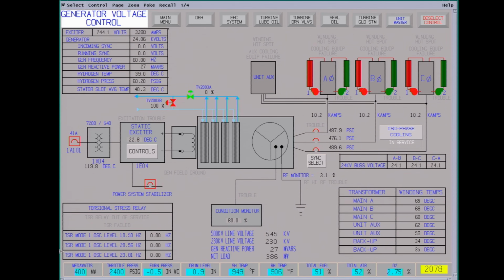Torsional stress relays. These were taken out a while ago. This is like at 10 hertz, 20, 23. The problem with generators, there can be big swings on the line. You can get hit with very high megawatt loads, also maybe 100 megawatts is the unit in a couple cycles. What that does is basically the rotor slows way down and it starts twisting the rotor. There have been some units in the past that failed from the shaft breaking from torsional stress problems. You really don't pick it up with instrumentation, it's too quick. But there's a lot of weird things going on in the power system.